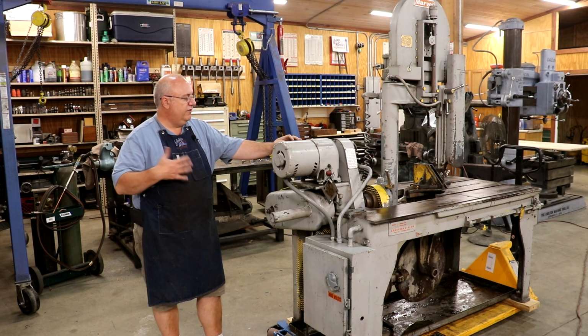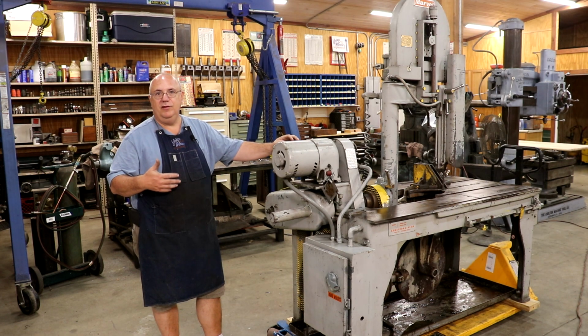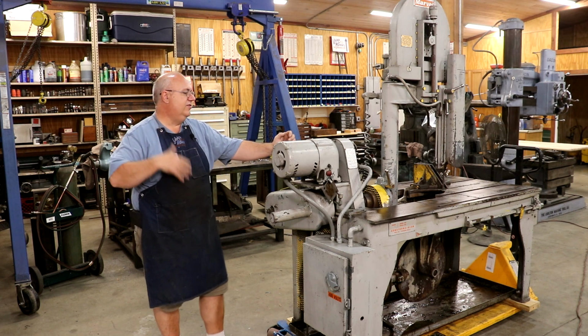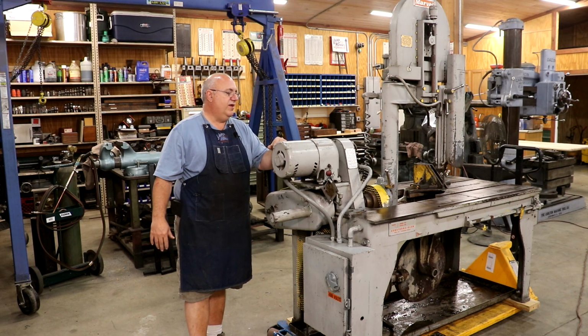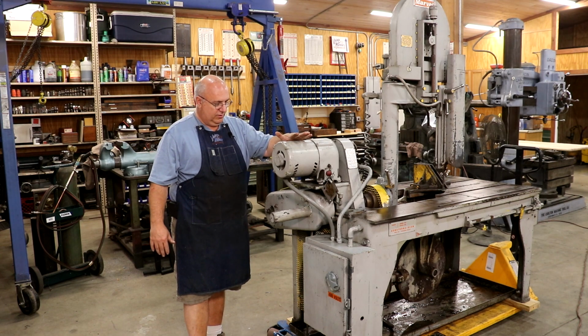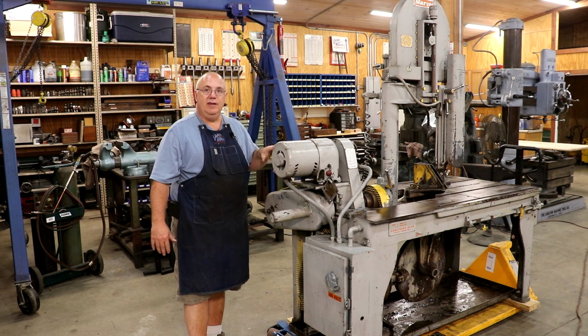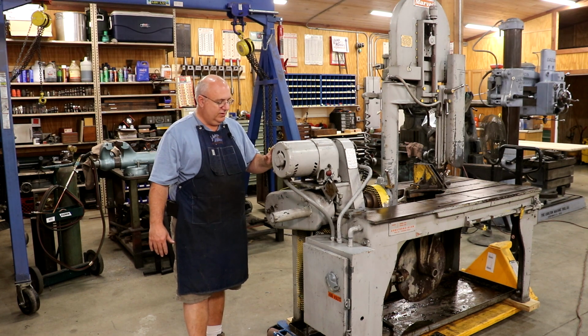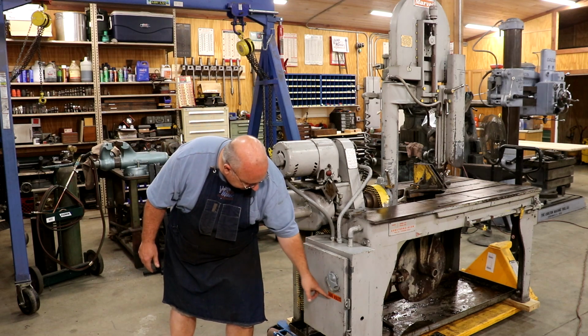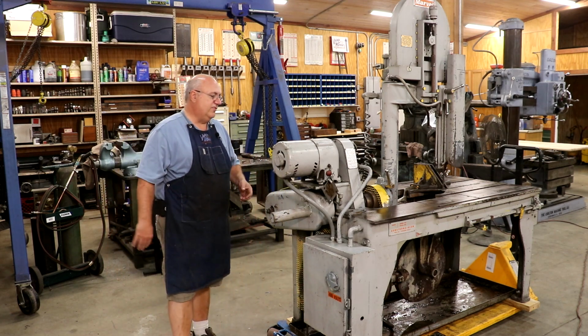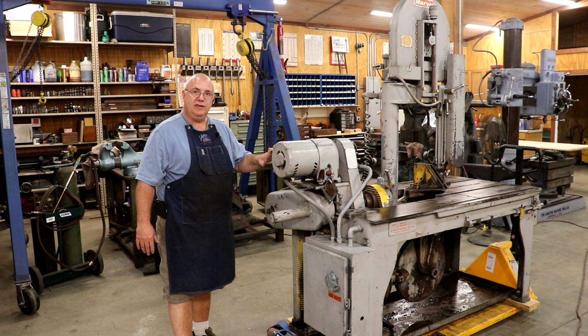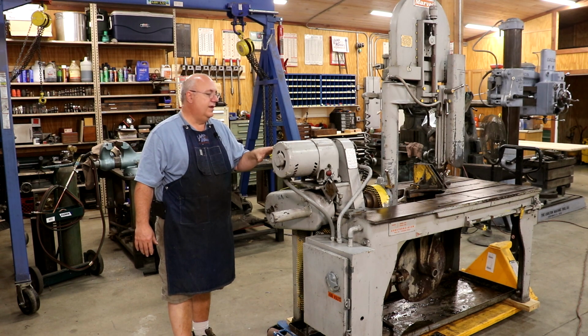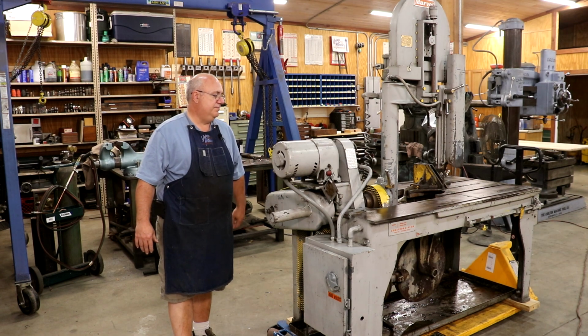In fact, I'm running off of a rotary phase converter, an American Rotary phase converter that we've got in here, that takes my regular 220 volt single phase, converts it to 220 volt three phase, and that's what I'm running stuff on. So we're going to have to change the wiring in the motor. Now, most motors are set up where they can run on either low voltage or high voltage, but you have to do some rewiring of the motors to do that. This one here got a sticker on here, 480 volts. I'm sure that's what it is, so we're going to go ahead and check this thing out and get it swapped over so that we can run it on the voltage that I'm running in my shop.